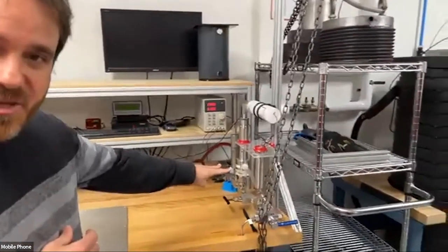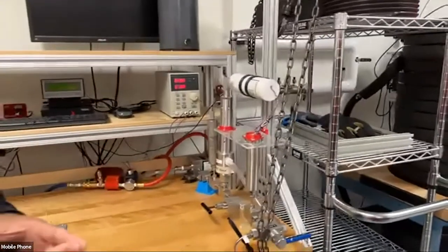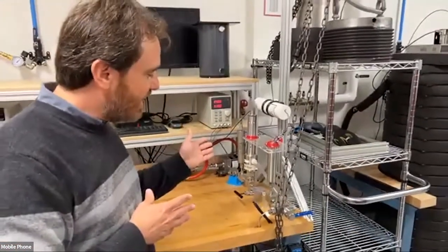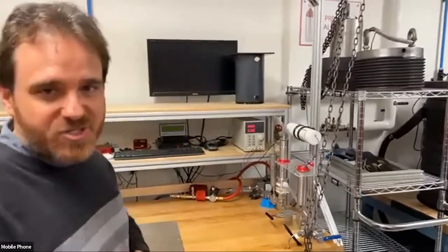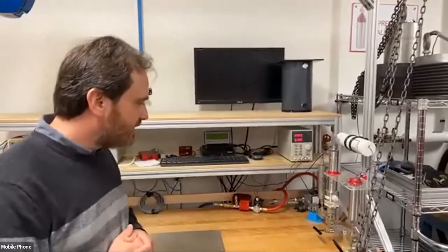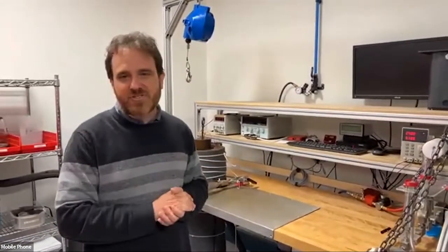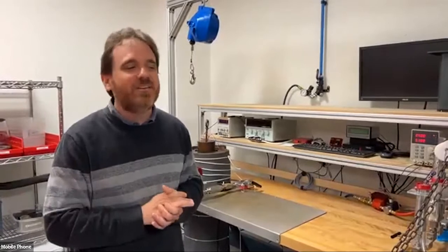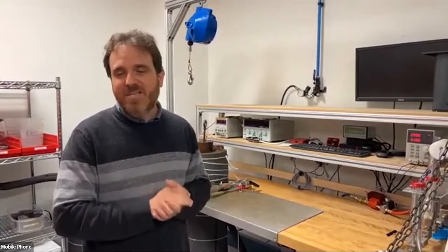And over here we can see the reference standards that we use for this system. These are 10K dbar Paroscientific transducers, as well as a Paroscientific transmitter that we use for QA checks and for the readouts here on the monitor that you can see here. So that basically summarizes the entire cycle here with the pressure calibrations, which obviously we use pressure data in order to derive depth, which is possibly the piece of data that most oceanographers are interested in. And yeah, that basically summarizes that.